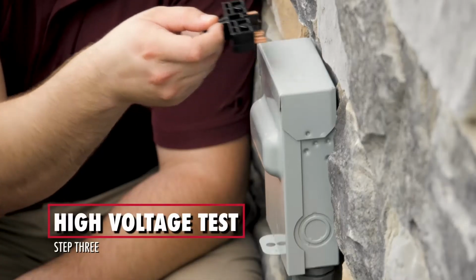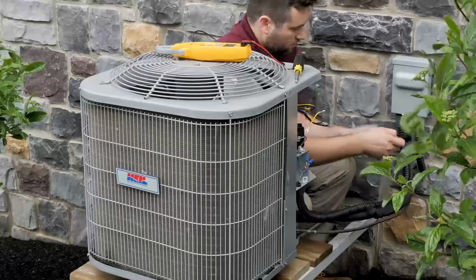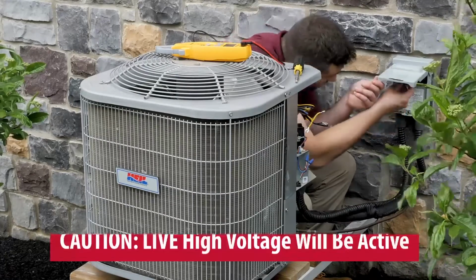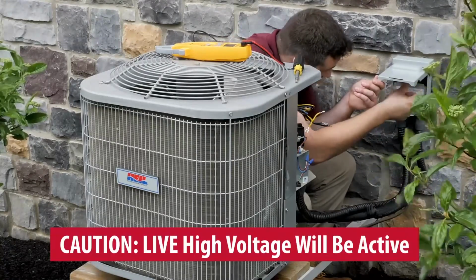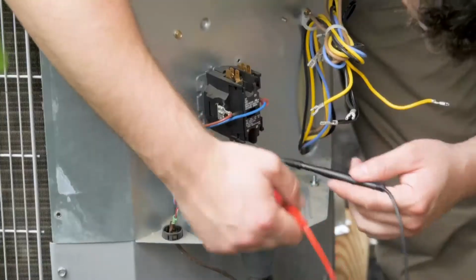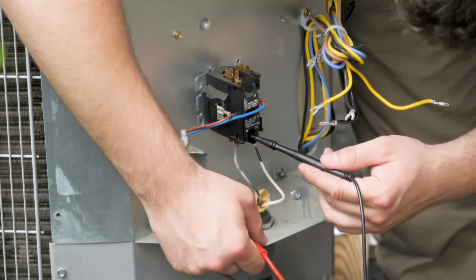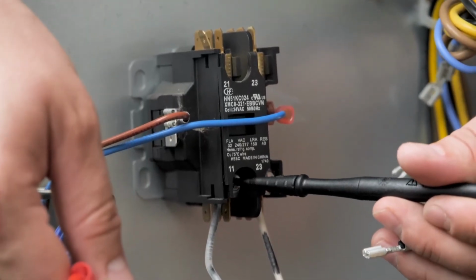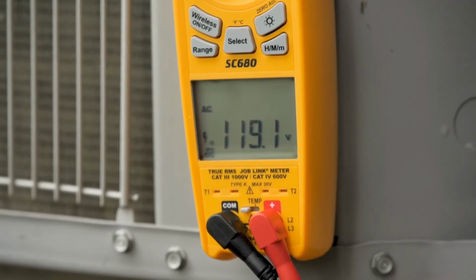Now we will go to the high voltage tests. You will have to put the disconnect back in first. Be careful, as there will be live high voltage in this system. Take one meter lead and place it on the L1 terminal and check to ground. You should have 120 volts on your screen at this point.